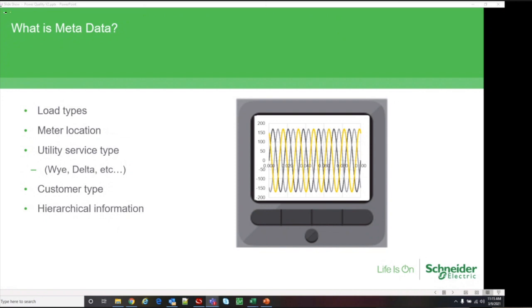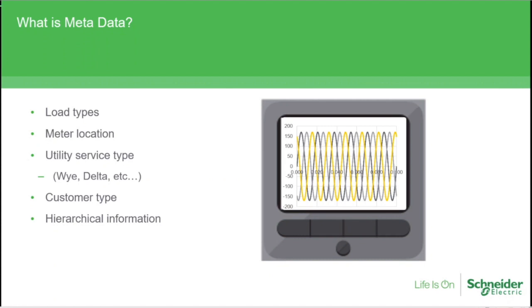So then when we get into metadata, this is more information, like where the meter is installed and the type of equipment you're monitoring. So load types, like an industrial manufacturer with arc furnaces or large motors. If you're dealing with distributed or transmission energy resources, you're dealing with different types of inverters, and all these loads can have different effects on the system. Then you also want to know your meter location and its relevance to your loads. Most power quality monitors are installed at the point of interconnection, as that's your legal agreement point. It's where you want to monitor and capture harmonic and swell events, not necessarily at the customer load.